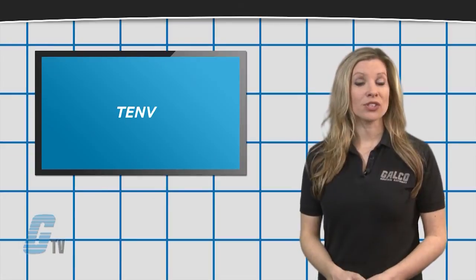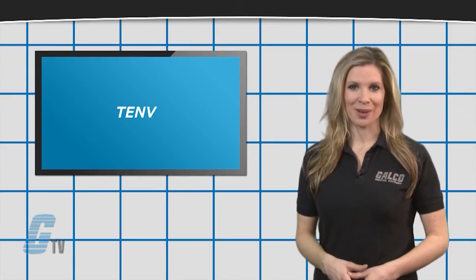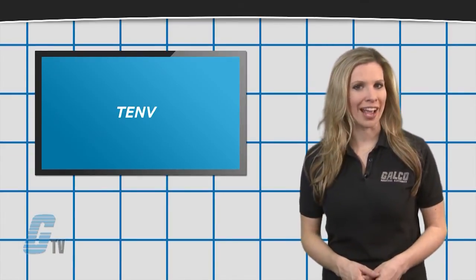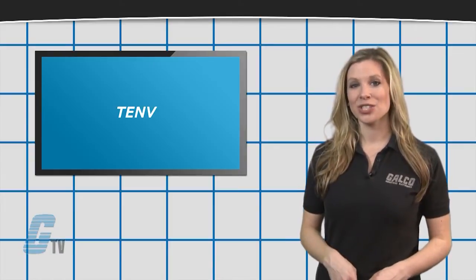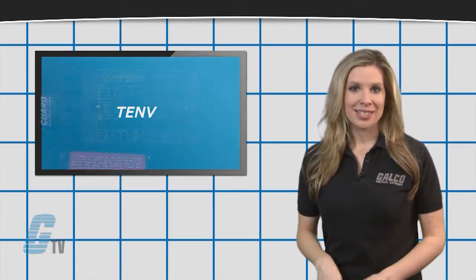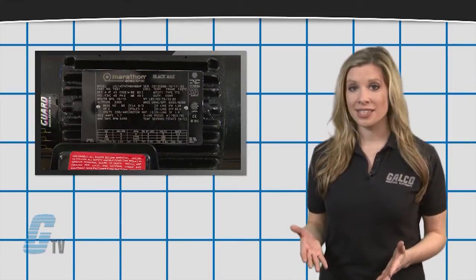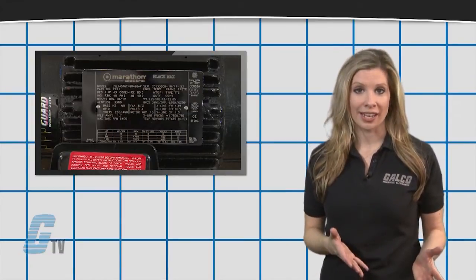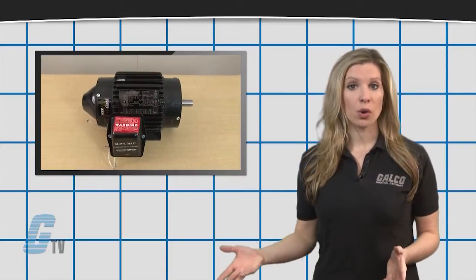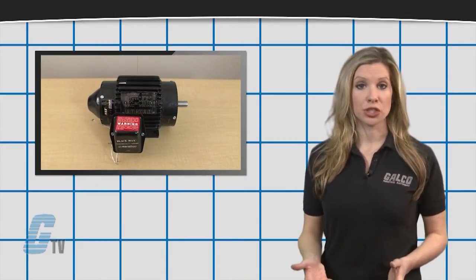The TENV motors offer greater protection from air contaminants and water spray and use thermal conduction to dissipate heat. Some TENV motors may use fins or higher heat resistant components to prevent overheating. These motors generally are lower in horsepower when compared to the other two.